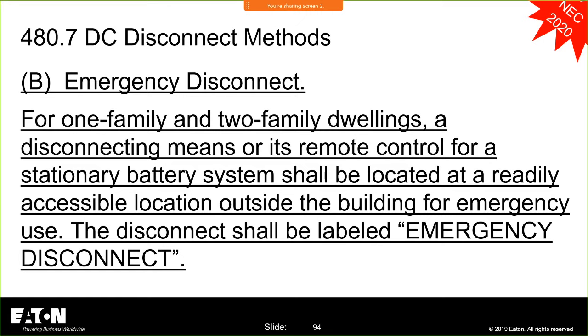But it says they need to be grouped for that, but it doesn't really, in my opinion, address the DC and the generator, saying that you need to group all of those together. And I don't see anything in 445 or 480. So I don't know if anybody out there in YouTube land or in chat land on WebEx has an opinion on that, but in my opinion, I don't see any reason that you would have to group all of those together.